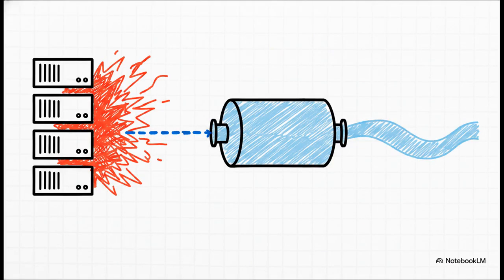But here's the thing. Providing emergency water is actually only half the story. We really have to look at this tank as a highly dynamic energy storage device. Modern AI data centers are incredibly unpredictable. Unlike older, traditional data centers with steady, boring workloads, AI servers running high-performance GPUs, like the H100 or the B200, have these wild minute-by-minute fluctuations in their computational load. And naturally, that means wild fluctuations in their heat output, too. Now, if the total volume of water in the cooling pipes is too small, these sudden heat spikes will cause the water temperature to just swing wildly out of control. The chillers then try to furiously chase these rapid temperature changes. It's a huge headache that engineers call hunting, and it leads to extremely unstable capacity control.